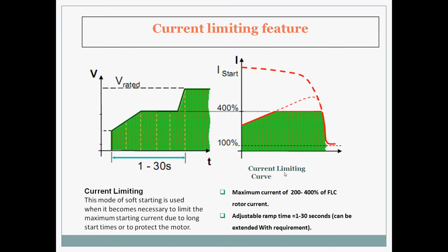Current limiting feature: you can see for other starters, the current limiting is like that. Starting with a huge current, then a very small current, then the current increases in that manner. But here in the soft starter, the current increases in a very gradual manner, so there is no surge observed. Maximum current of 200 to 400% of FLC rotor current. Adjustable ramp time is 1 to 30 seconds, and can be extended with the requirement. The mode of soft starting is used when it becomes necessary to limit the maximum starting current due to long start times or to protect the motor.